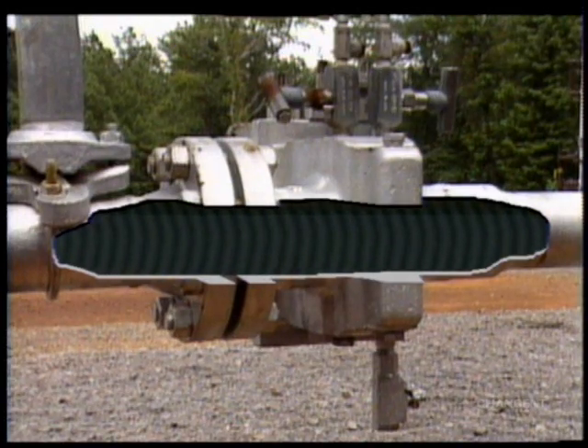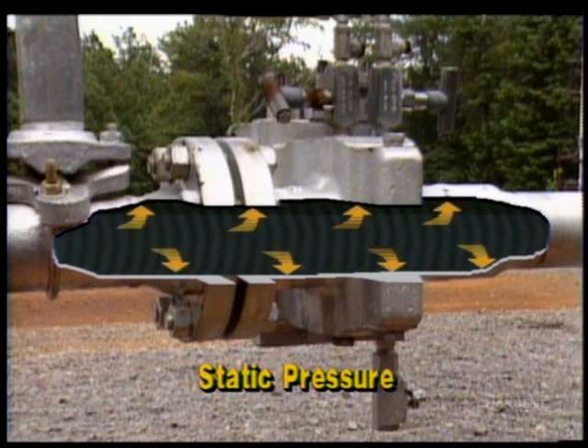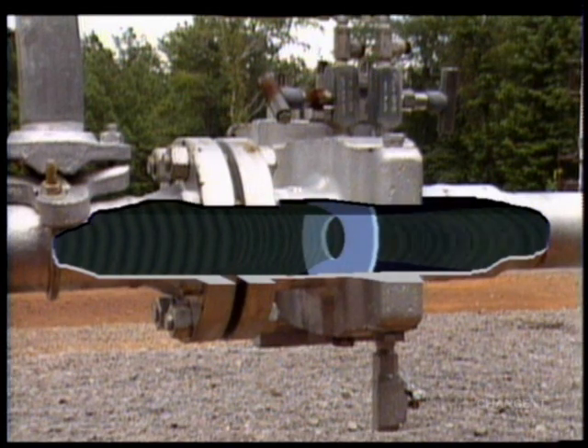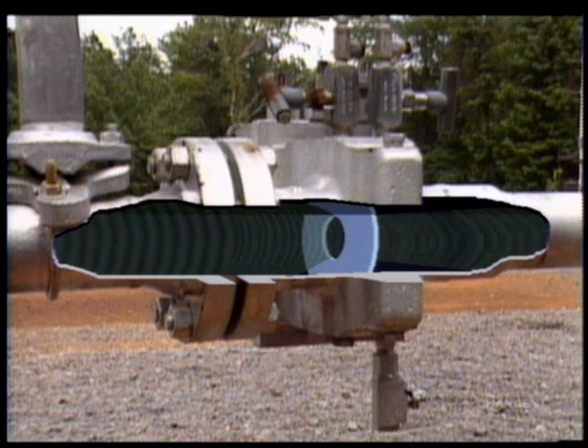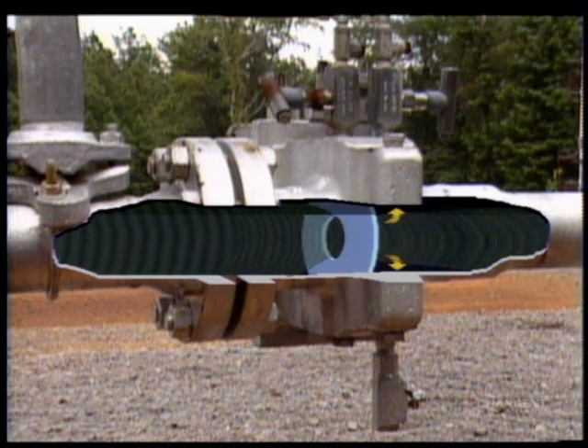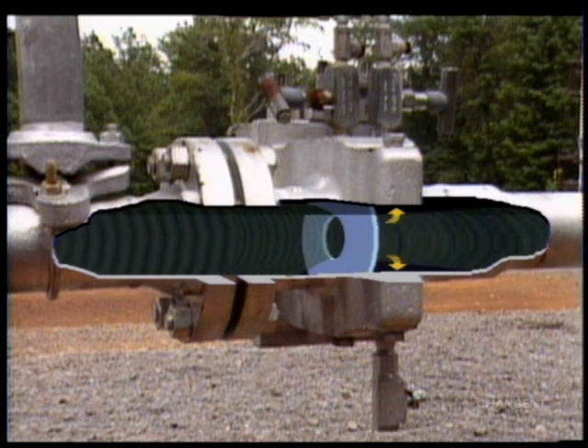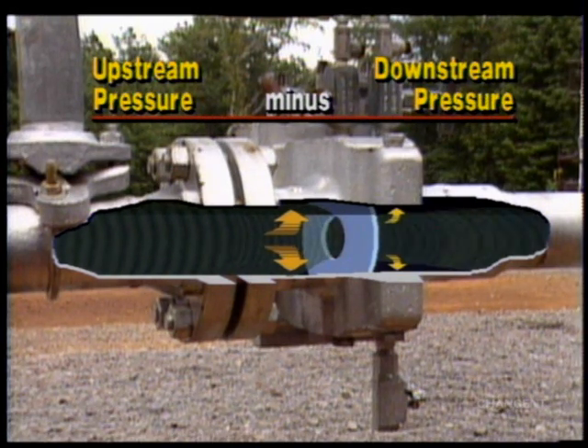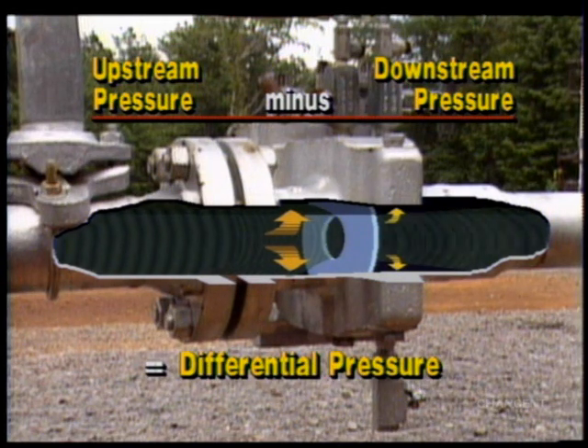Fluid flowing through a pipe exerts a constant pressure called static pressure on the walls of the pipe. When a constriction like this orifice plate is placed in the pipe, the velocity of the fluid is increased. The higher velocity fluid on the downstream side of the orifice plate creates a static pressure lower than the static pressure exerted on the upstream side. The difference between the upstream and downstream static pressures is known as differential pressure.